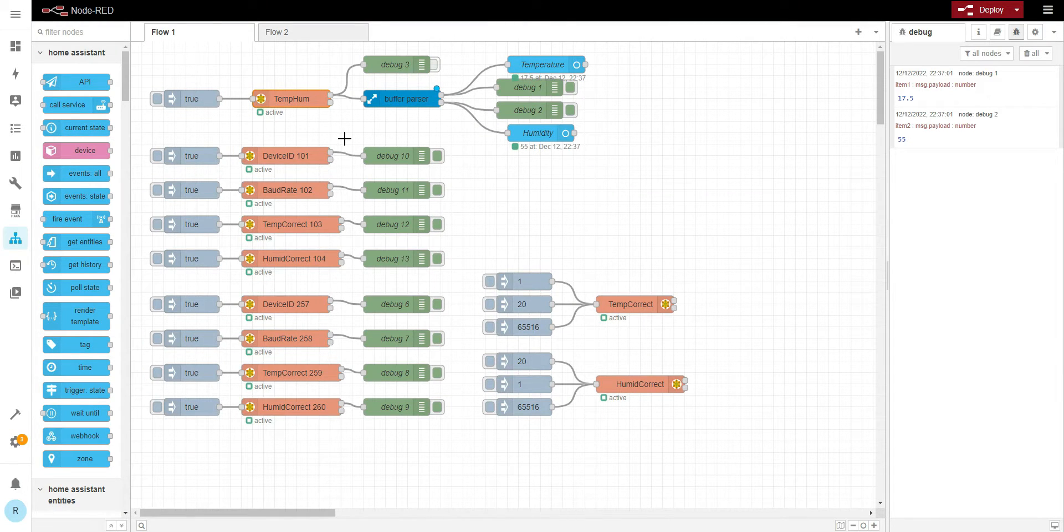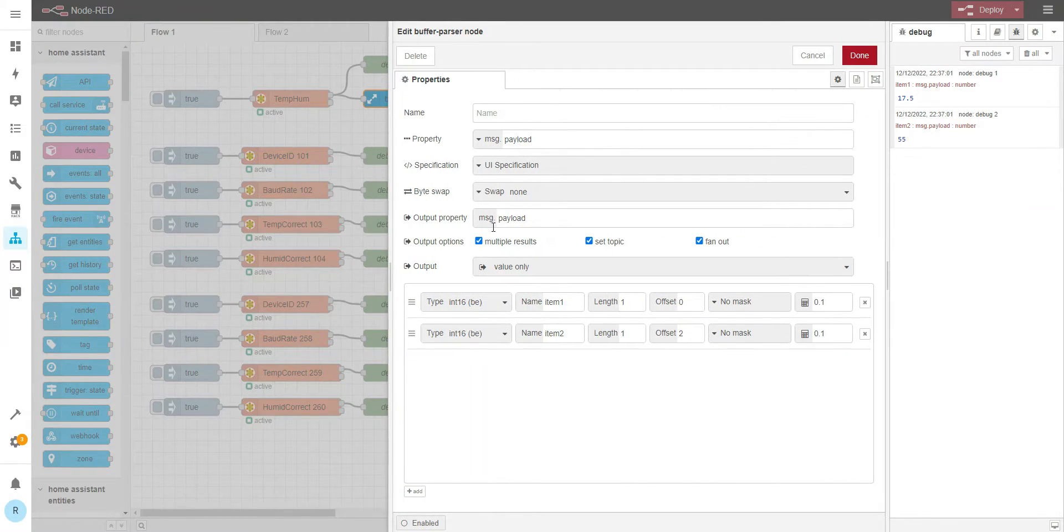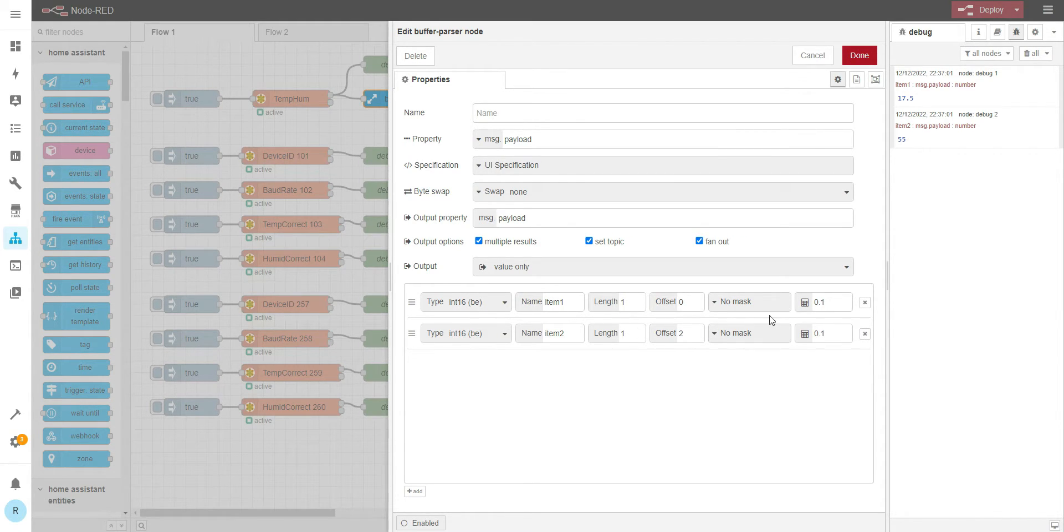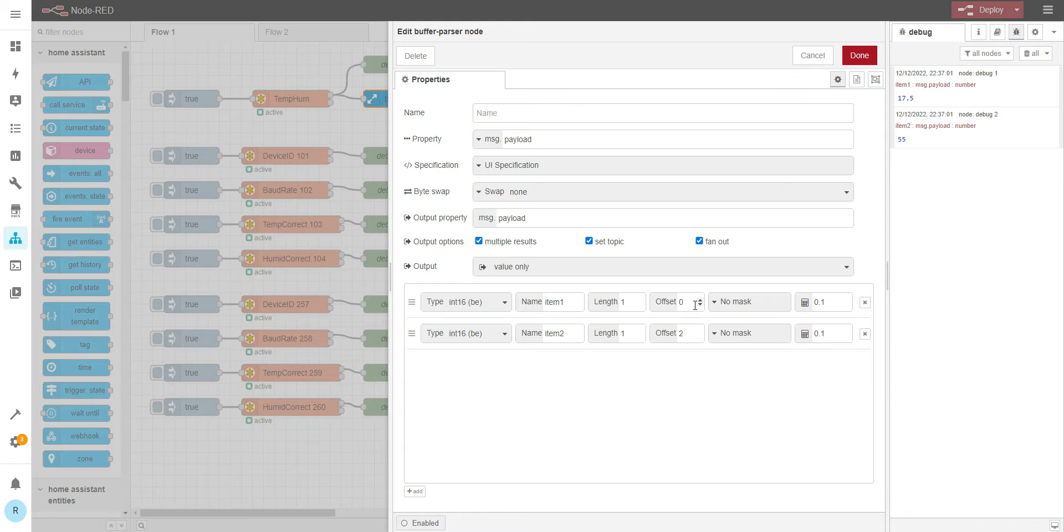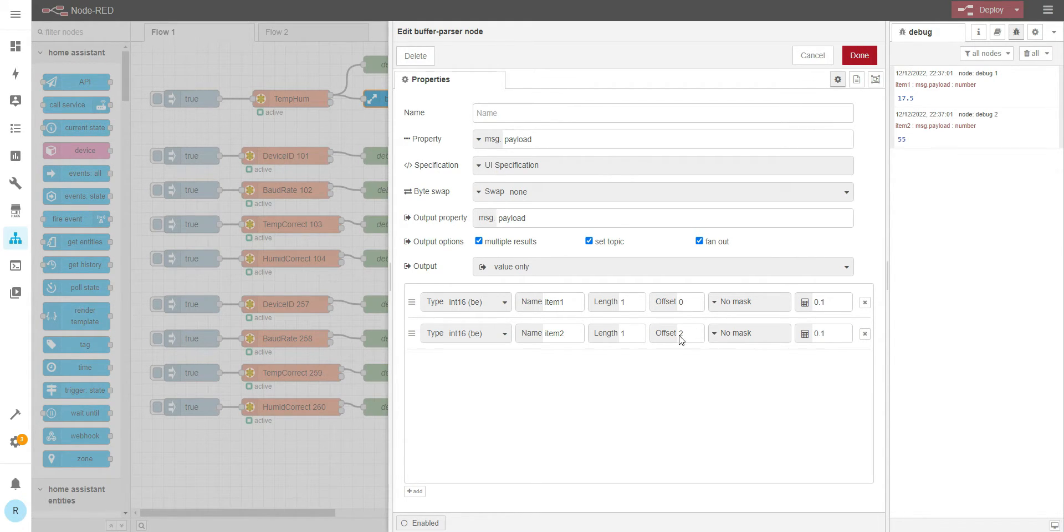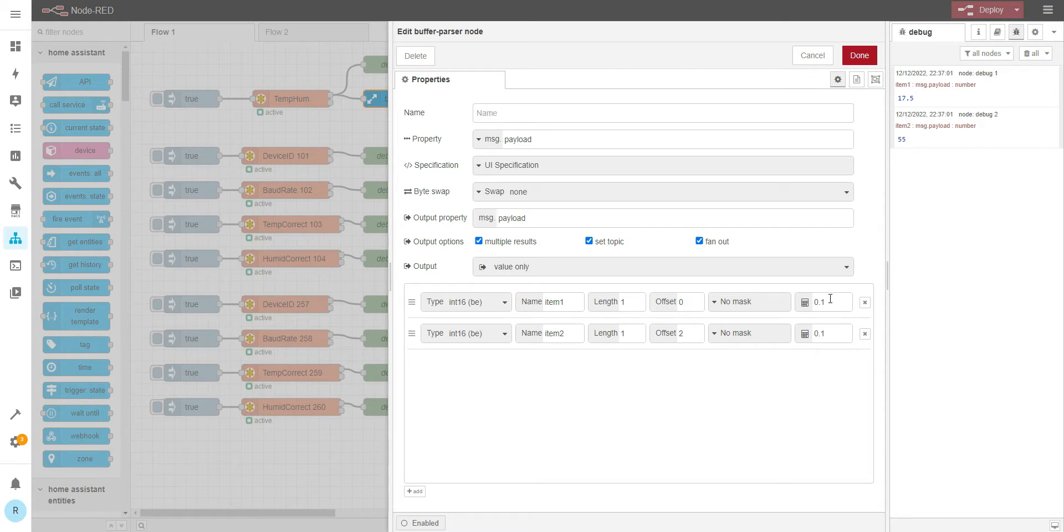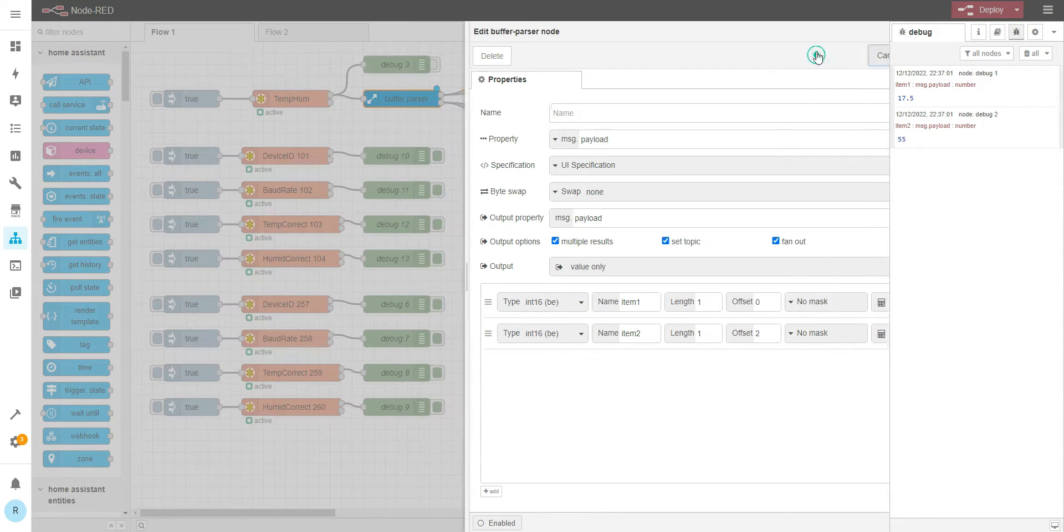Let's try to read the temperature. One more thing, buffer parser. If we want to read the integer value, then this is the correct setting. Offset is 2 because every register has two bytes. So first register, second register will be offset 2 because it's two bytes offset from the first one. And this is the value multiplier.